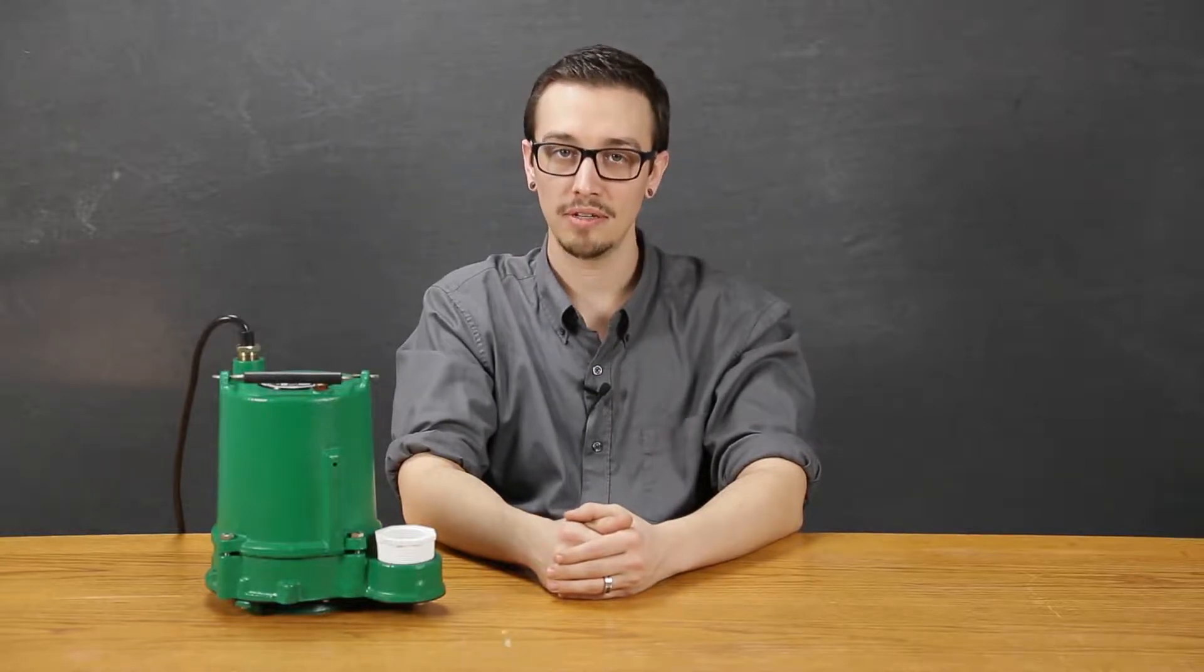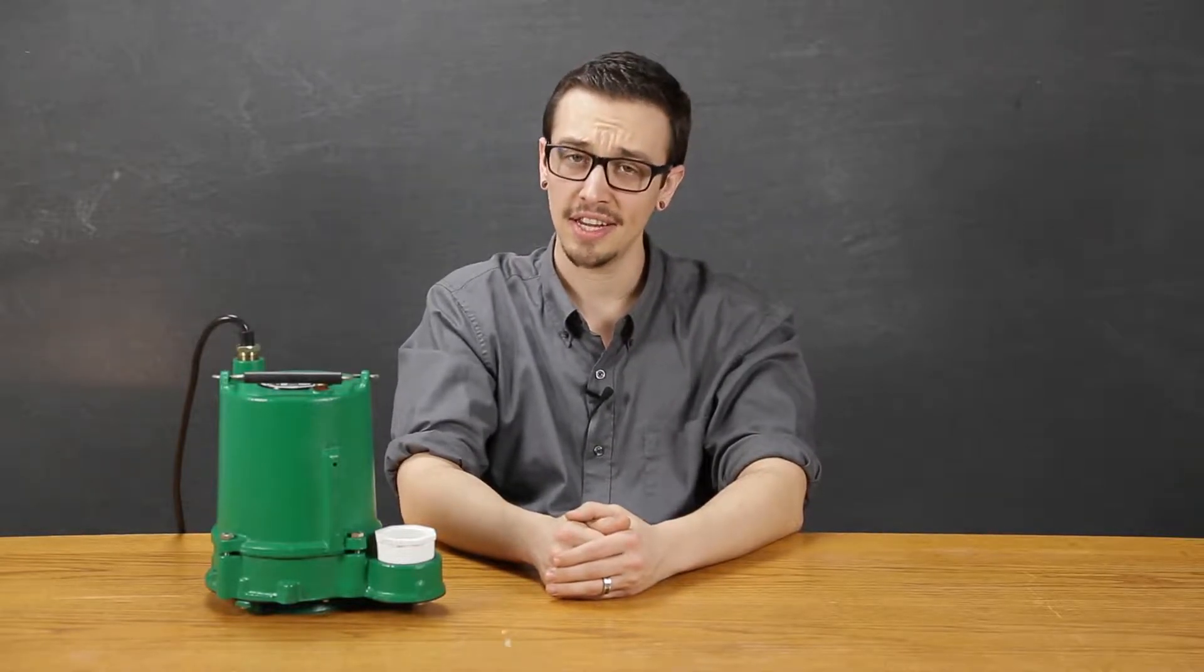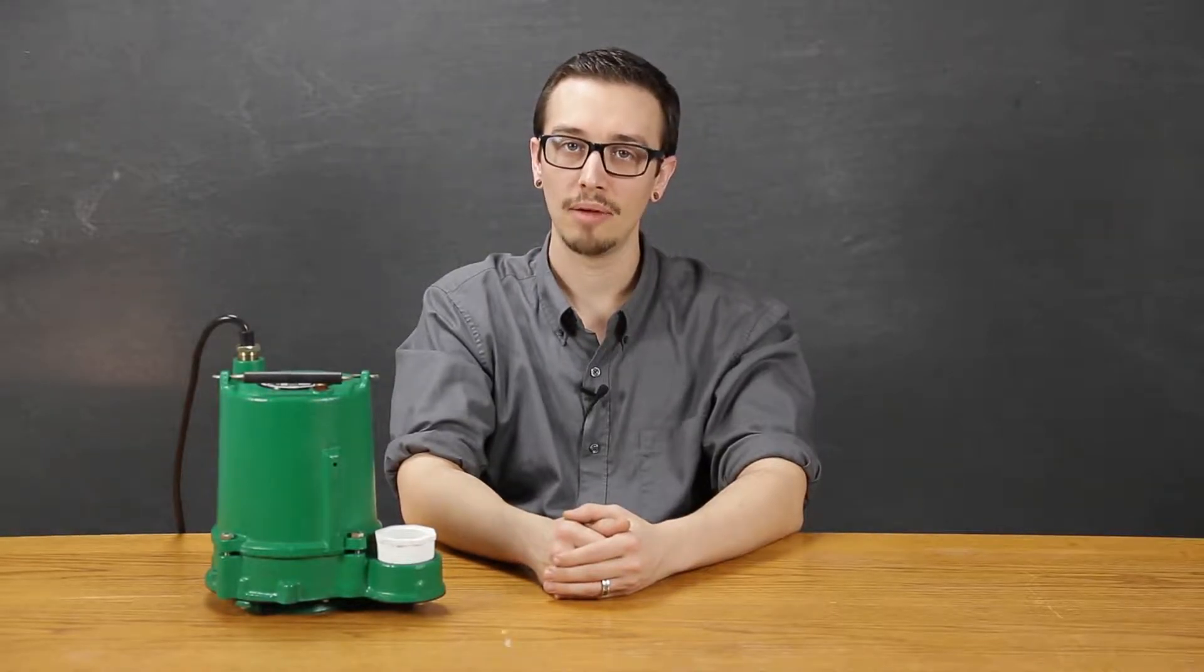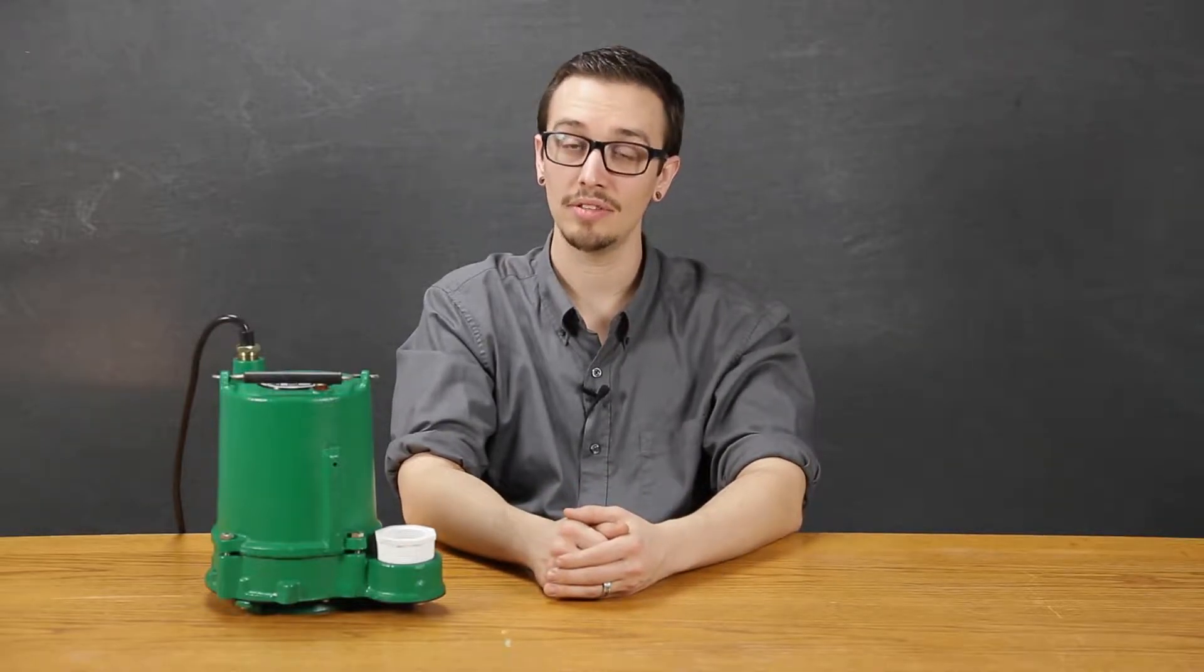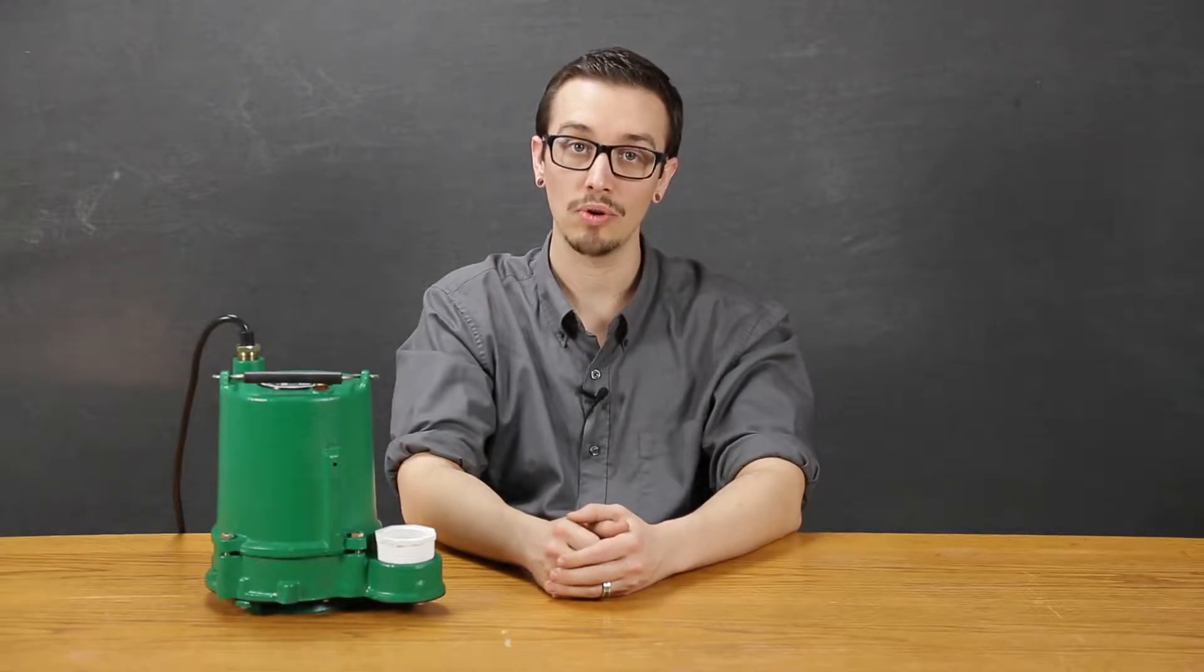The minimum sump diameter recommended for these pumps in a simplex configuration is 18 inches and 30 inches in a duplex configuration. By maintaining this minimal diameter, we are ensuring that the equipment has enough room for proper operation and helps to eliminate cord entanglement.